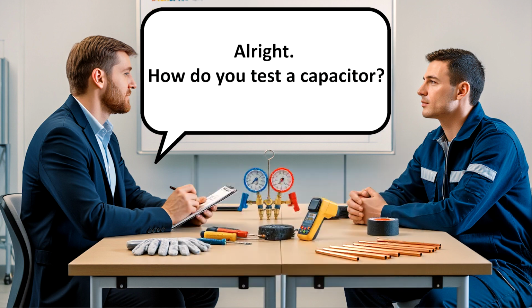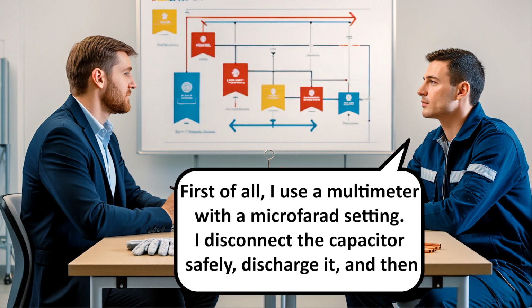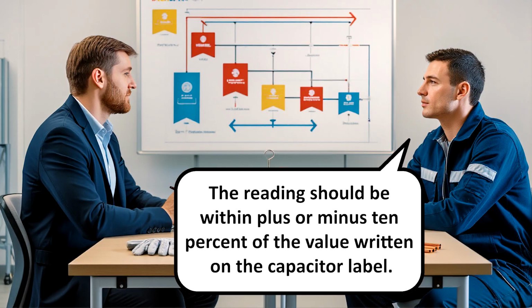All right, how do you test a capacitor? First of all, I use a multimeter with a microfarad setting. I disconnect the capacitor safely, discharge it, and then test it. The reading should be within plus or minus 10% of the value written on the capacitor label.